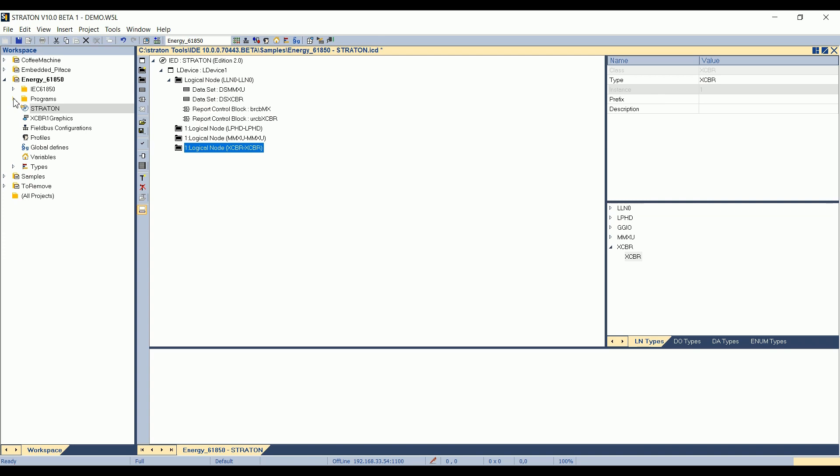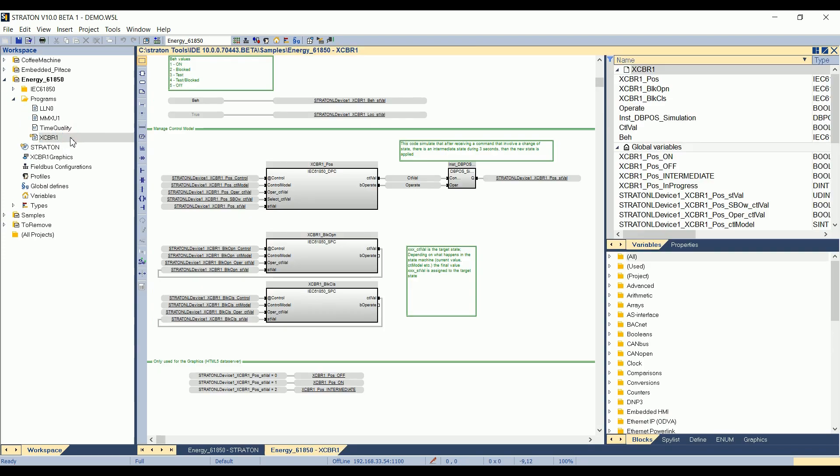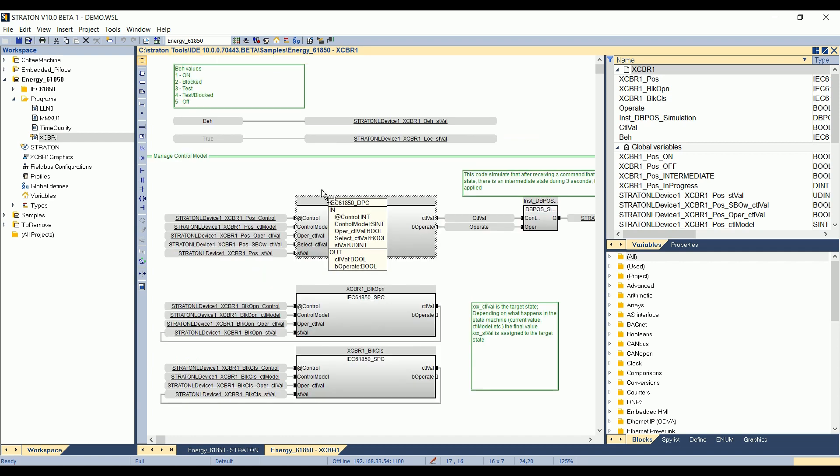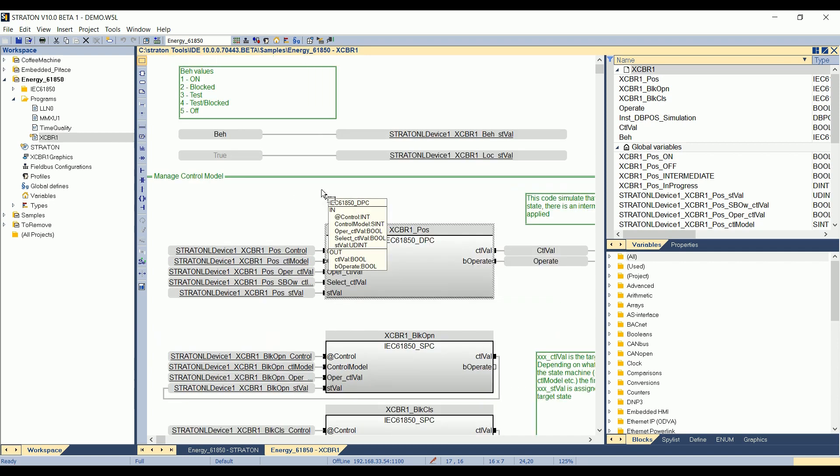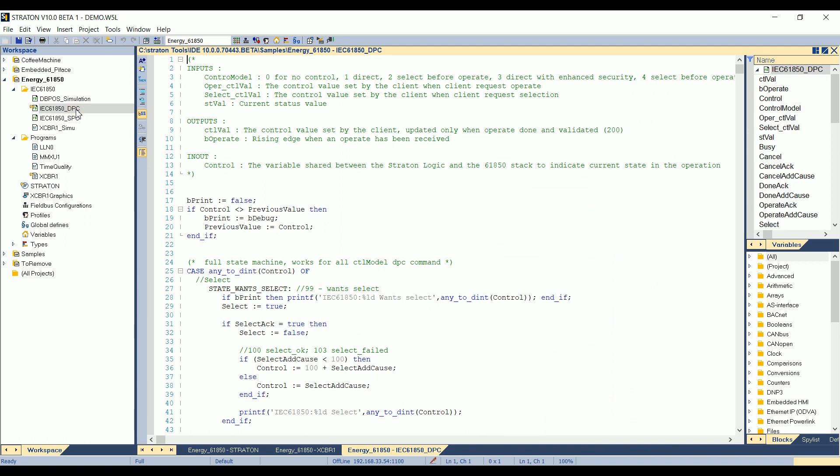In the programs here, we have the XCBR1 project. I can see that commands are managed here. If I click on the plus key, I can zoom. The state machine is managed by a UDFB, a user-defined function block, which is here, IEC 61850 DPC. This state machine manages double point controllable operations sent from the client.